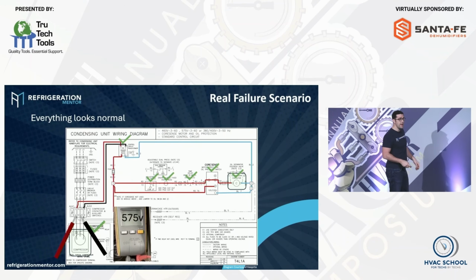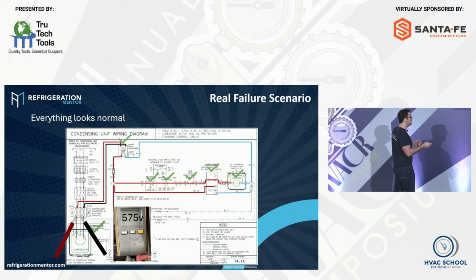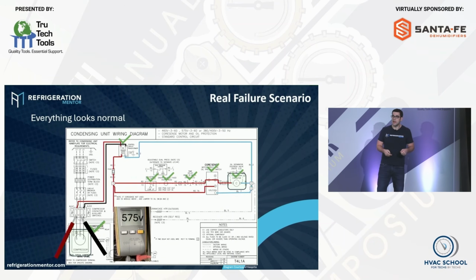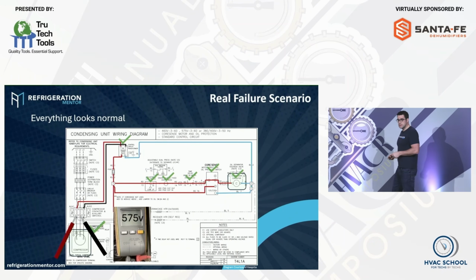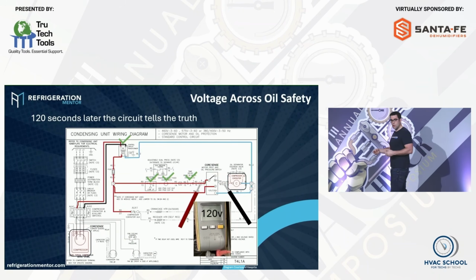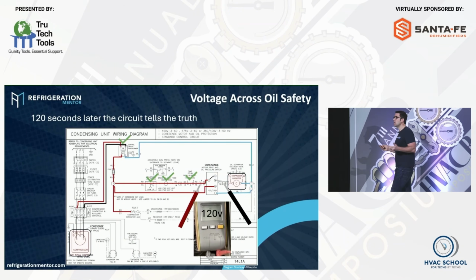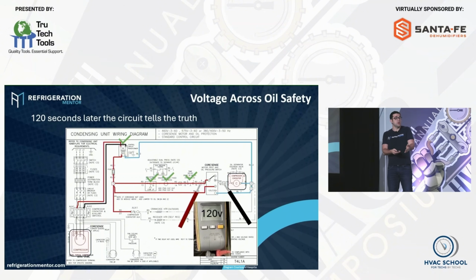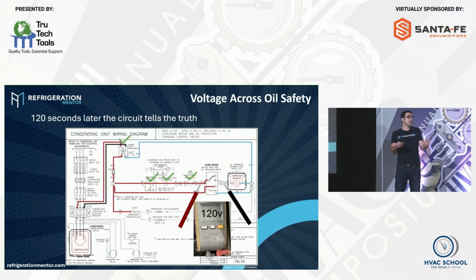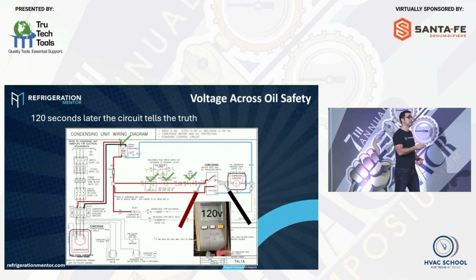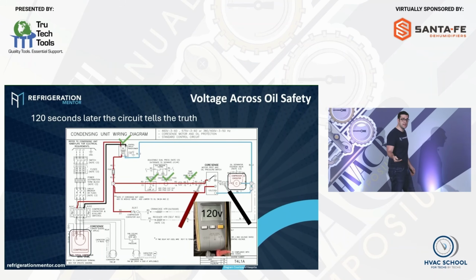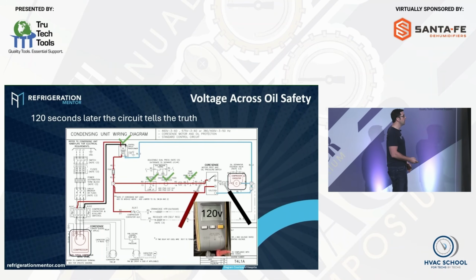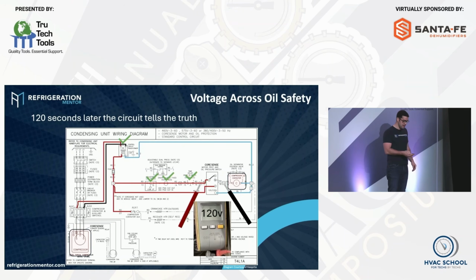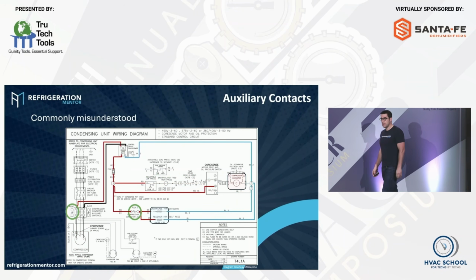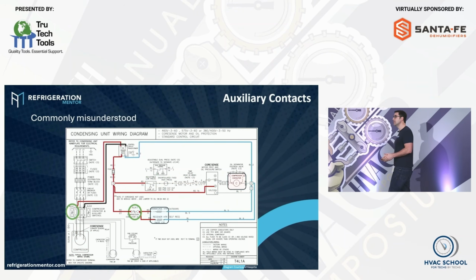A real scenario, everything looks normal. I check my meter, I've got power on my load side right now. But all of a sudden it trips out after 120 seconds. But it was working there a few minutes ago. You checked it, oh, it's running right now. But all of a sudden you have a time delay or you have an oil failure like this, it trips and tells the truth. We've got to find that, that is our job. It's so important. Auxiliary contacts, another thing that is misunderstood.